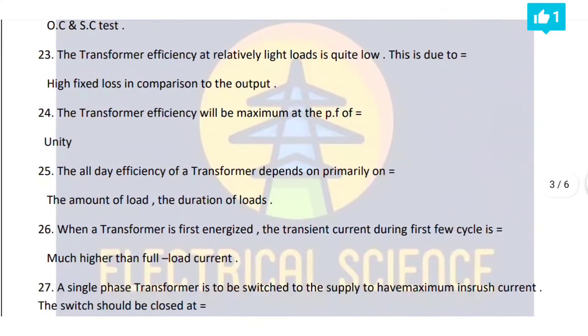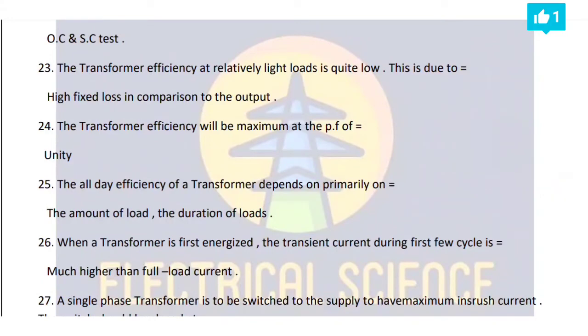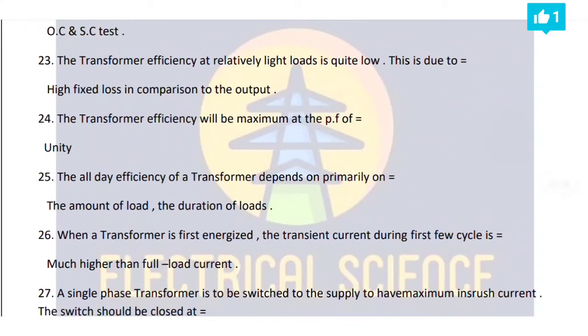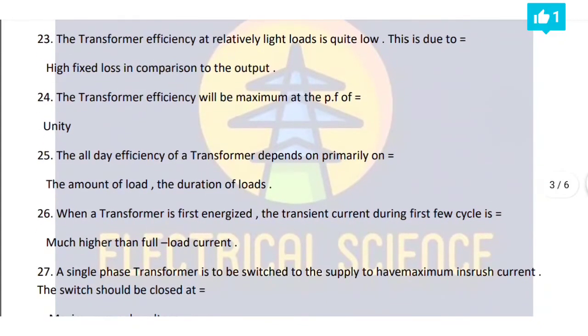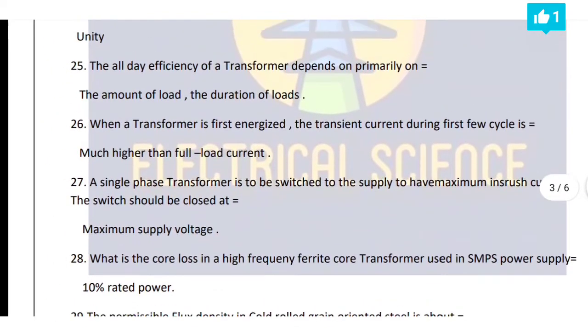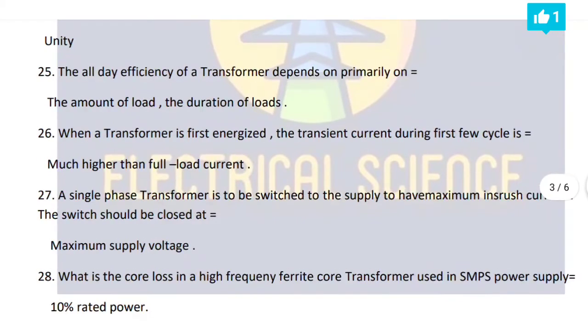Okay. 23rd point, the transformer efficiency at relatively light loads is quite low. This is due to high fixed loss in comparison to the output. Okay. 24th point, the transformer efficiency will be maximum at the PF of unity. 25th point, the all day efficiency of a transformer depends primarily on the amount of load and the duration of loads. Okay.